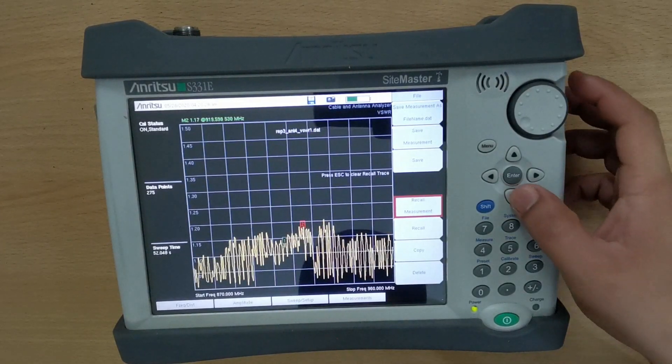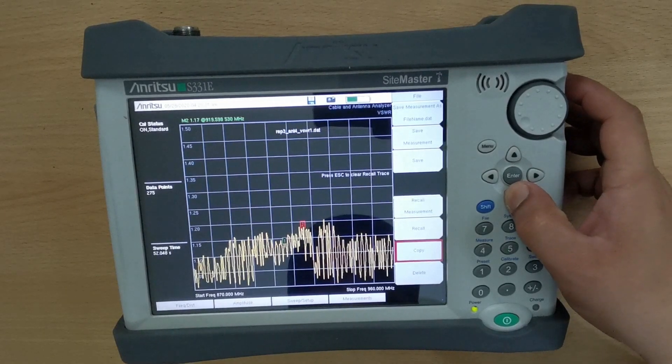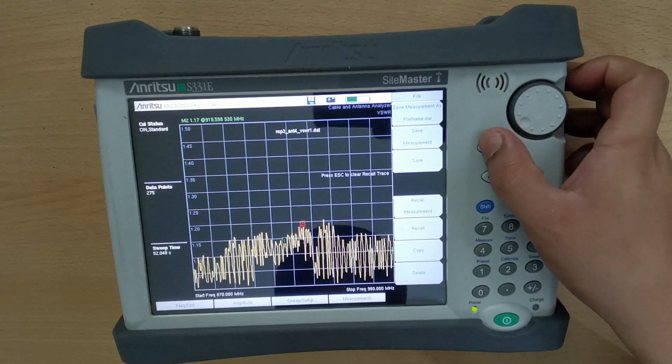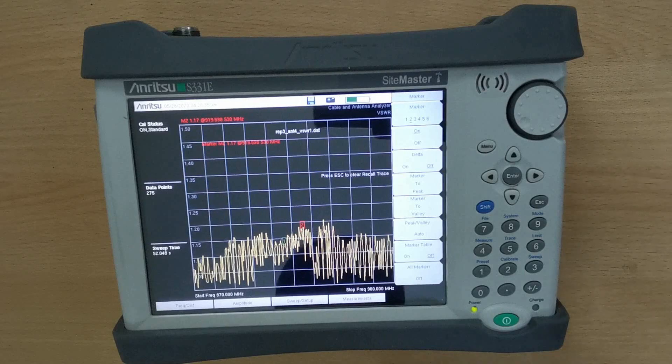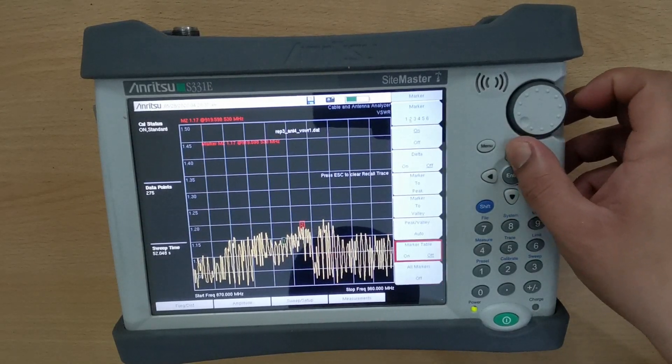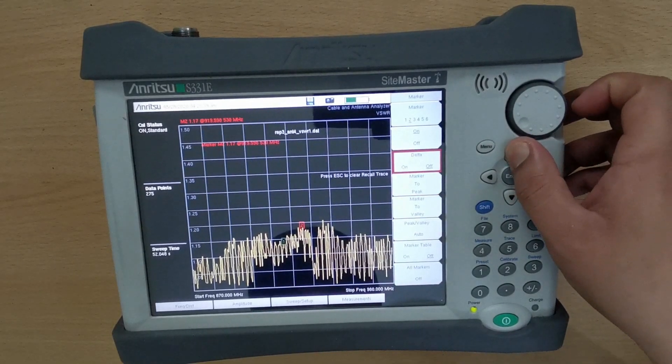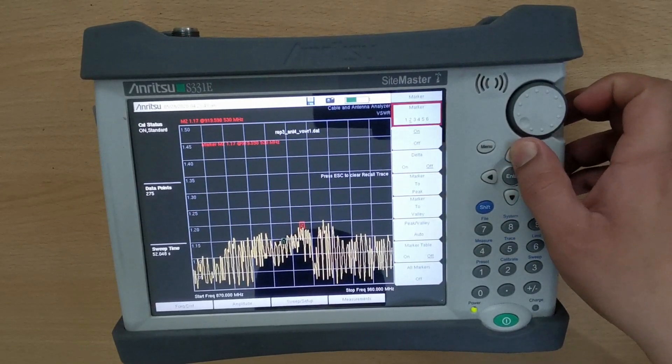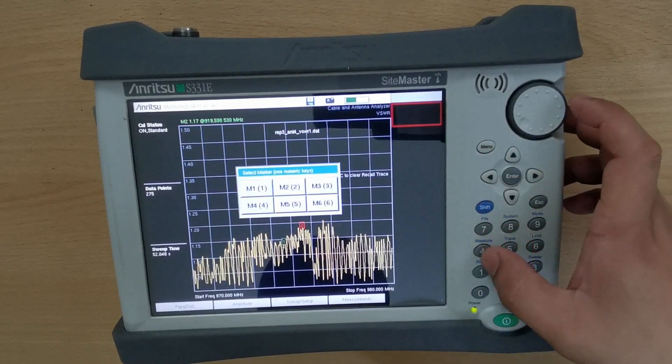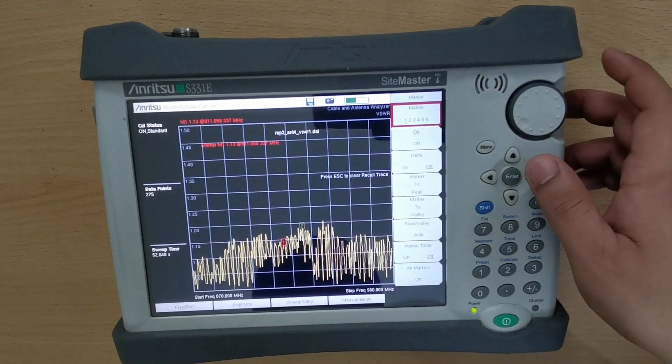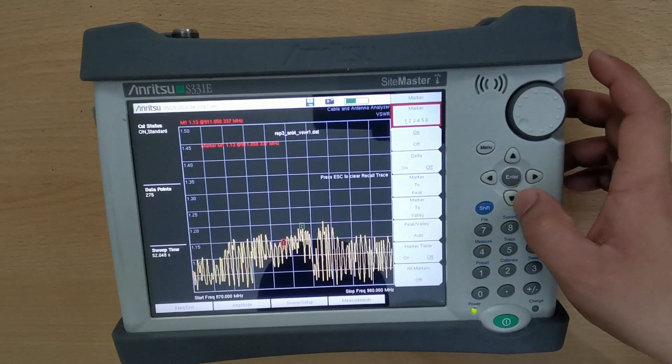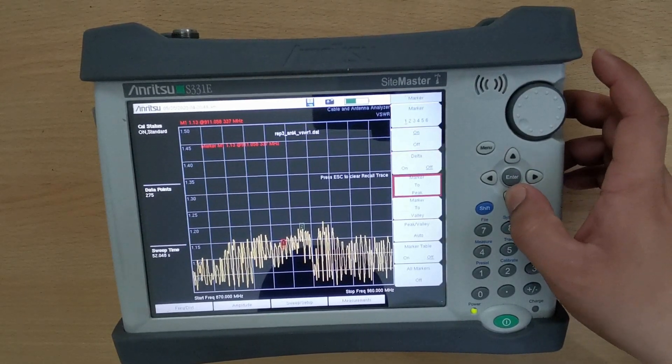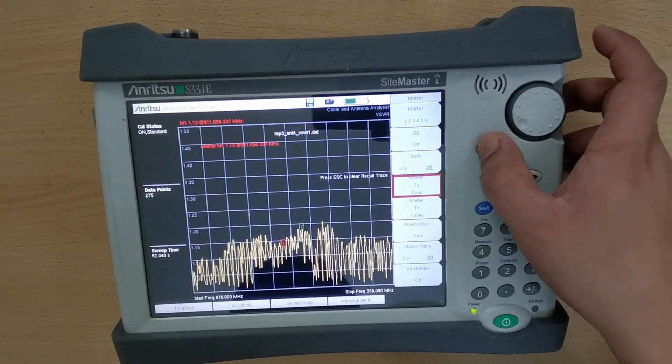To check the value, go to Marker tab and press Menu. Set the M1 to be the reference marker. To check the maximum peak value of the waveform, navigate to Marker to Peak and press Menu.